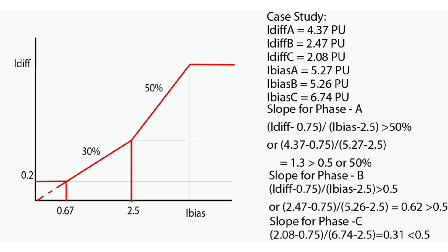For phase C, using the same formula — (I_differential minus 0.75) divided by (I_bias minus 2.5) — which must be greater than 0.5: the differential current is 2.08 per unit and bias current is 6.74 per unit. The slope equals (2.08 minus 0.75) divided by (6.74 minus 2.5), which equals 0.31 — less than 0.5 or 50%. Therefore, the differential current for phase C remains in the restraining region.